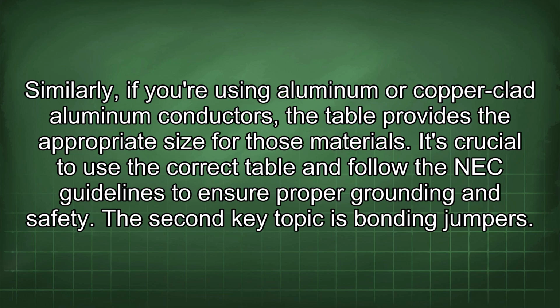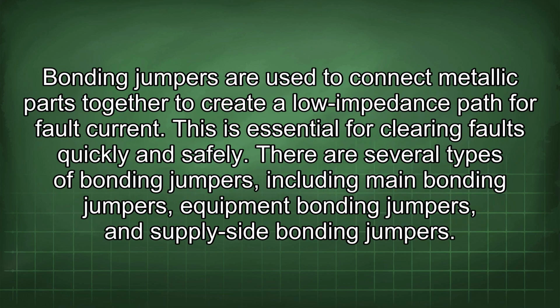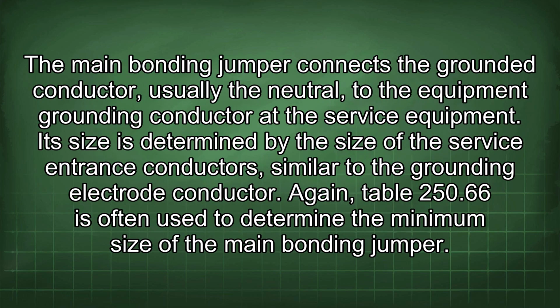The second key topic is bonding jumpers. Bonding jumpers are used to connect metallic parts together to create a low impedance path for fault current. This is essential for clearing faults quickly and safely. There are several types of bonding jumpers, including main bonding jumpers, equipment bonding jumpers, and supply-side bonding jumpers. The main bonding jumper connects the grounded conductor, usually the neutral, to the equipment grounding conductor at the service equipment. Its size is determined by the size of the service entrance conductors, similar to the grounding electrode conductor.